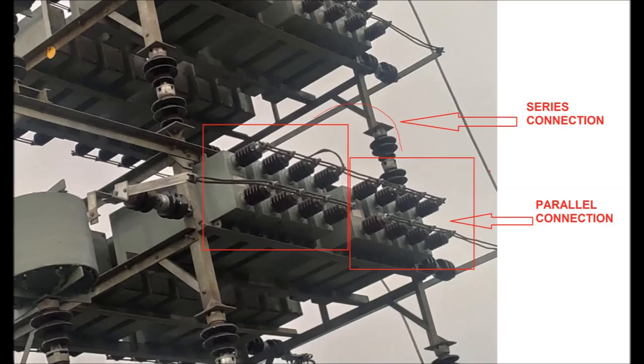How the capacitor units are connected in series and parallel combination has been shown in this figure. For one phase of one star connection, there exist eight capacitors in each phase. Four capacitors are connected in parallel combination, and another four are connected in parallel combination. These two parallel combinations are then connected in series in each phase of each star connection.